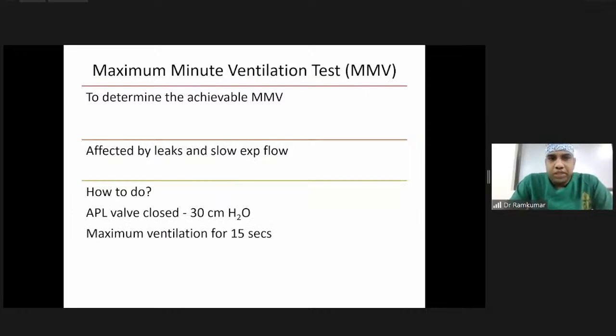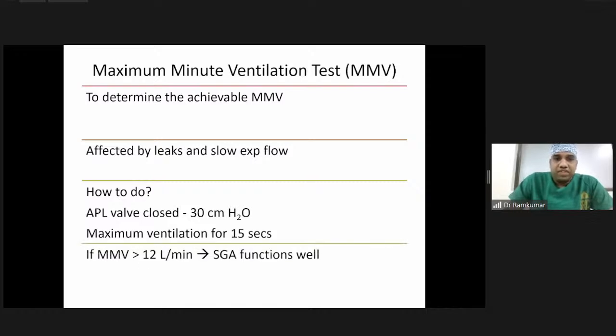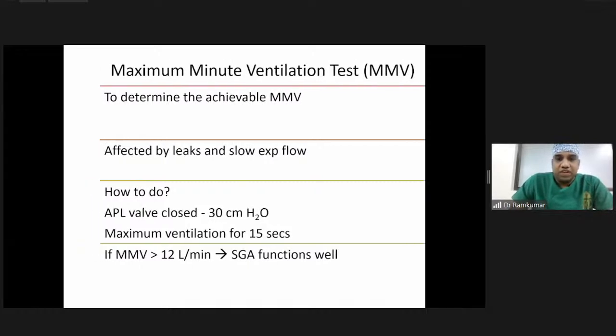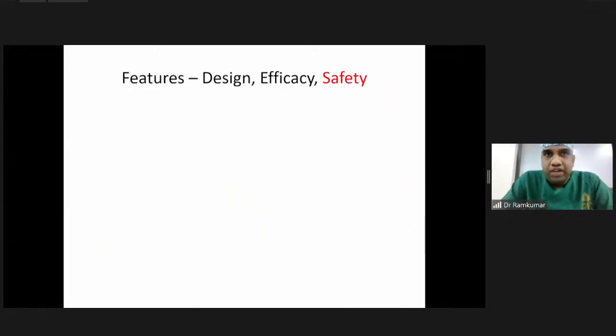How to do this test? You close the APL valve at 30 centimeter of water, then you do a maximum ventilation, like increase the ventilation for 15 seconds. And if you're able to see that maximum ventilation is greater than 12 liters per minute, that means that your supraglottic airway, the SGA, functions very well. These are 2 tests to identify the ventilation parameter of a particular device.